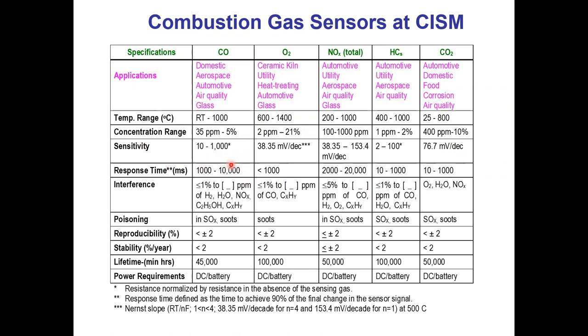If you're trying to detect in a dynamic environment like automotive exhaust, your sensor has to be very fast responding. But if you're trying to detect carbon monoxide above a threshold limit in an office or lab environment, the response time can be on the order of minutes or tens of minutes — we still don't get hazardous effects by being exposed to, for example, 25 parts per million of carbon monoxide over several hours. Obviously, interference is a big issue: can we detect selectively in a gas mixture?